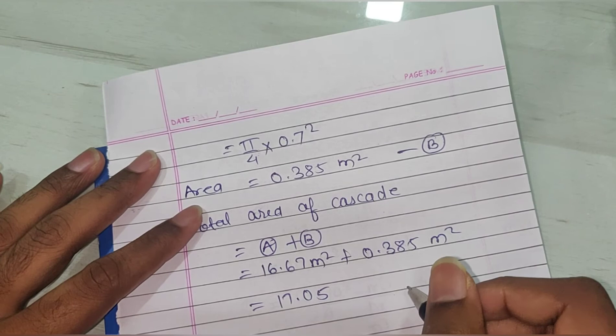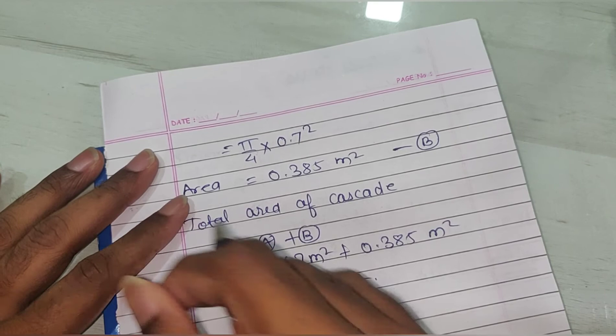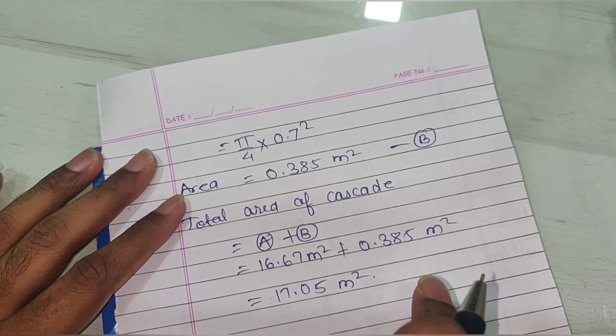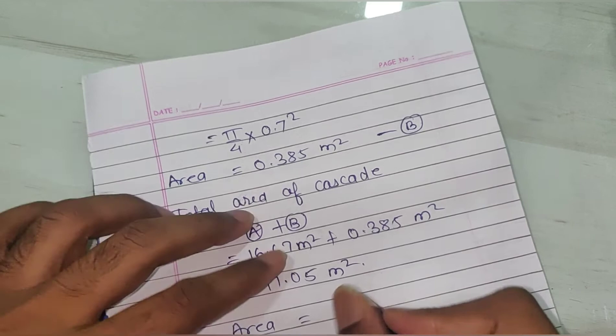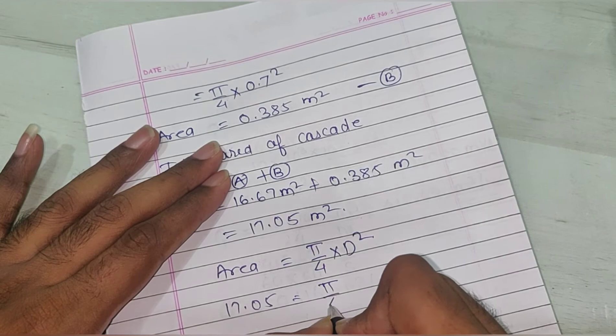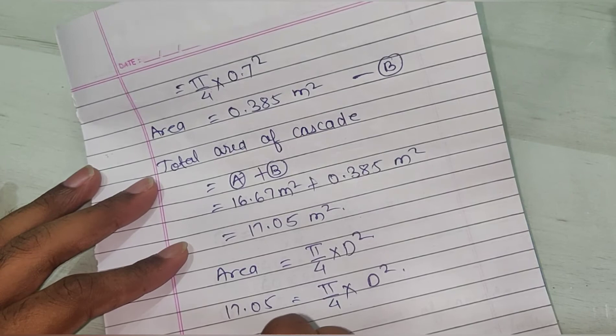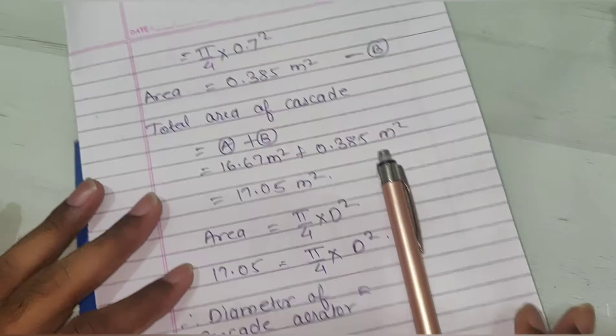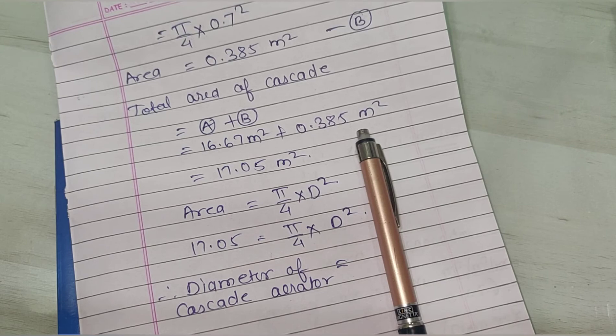Now we have to find the diameter of the total cascade area, which includes both the number of steps and the diameter of the central shaft and pipe. Using area equals pi by 4 into D squared: 17.05 equals pi by 4 into D squared. After calculating, the diameter of the cascade aerator comes as 4.66 meter.